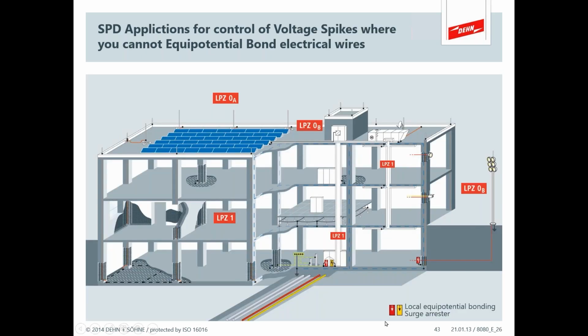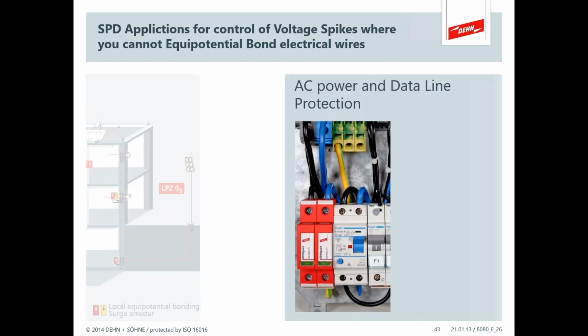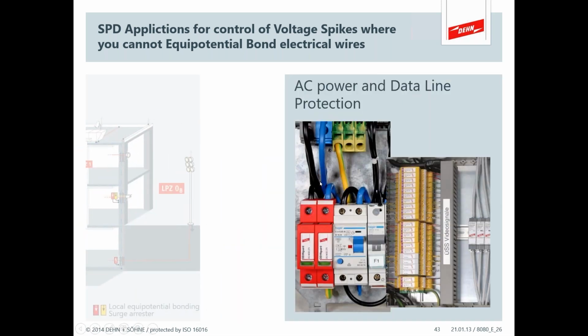But what about electrical wires? You can't bond electrical wire. You can't short them to earth to safely protect them. So you use surge protection devices. What that SPD does is provide equipotential bonding for what cannot actually be electrically bonded. You're controlling the voltage momentarily during a lightning event. Otherwise, it's acting as sort of your separation distance. It's your electrical separation distance. So you're controlling it only when it needs to be controlled, with lightning or surge damage. And that goes for all of your AC power lines as well as your data lines throughout a system.